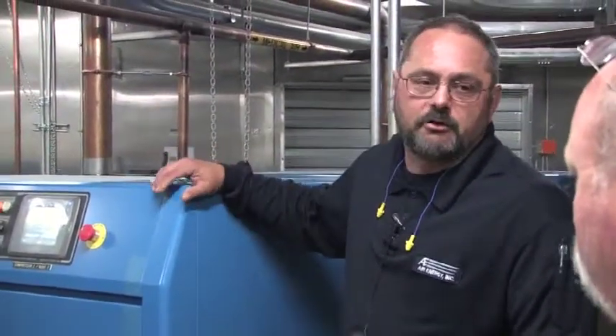Once we get everything running, there may be some tweaking of the exact settings. For example, the factory originally set those at 2 and 3 pounds for the trigger, and I've now widened it to 5 and 10. Because at 2 and 3, all of them were starting every time a drain fired. Don't need to have it do that. But you just need to understand the algorithm's a little different.